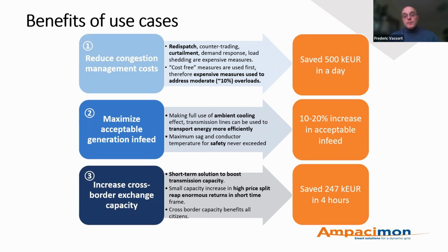Of course, by the same token, it also increases the in-feed of the available generation. We'll come back in a minute to the specific case of wind renewables, which have a nice correlation with DLR. It can increase cross-border exchanges, which is a key factor this winter. It will be probably even more important next winter. DLR is a great way for TSOs to meet the 70% target set by ACER, which they will have to comply with very shortly, simply by allowing the lines to come closer to their real true capacity.